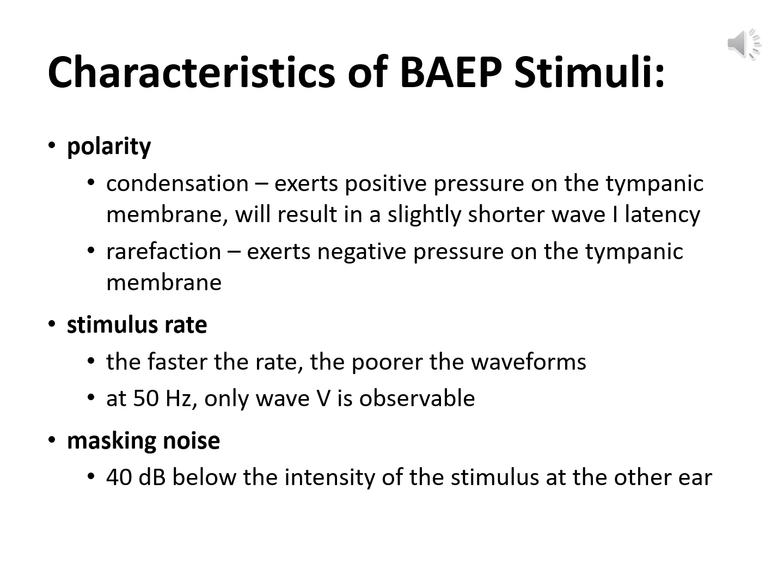In most populations, a stimulation rate of 8 to 10 hertz is recommended. We often use 11 hertz as a starting point. This means we present 11 clicks per second. We can slow the stimulus rate in young children and lower it even further in neonates. Changes to the stimulus rate must be noted on the tracing for the person who is interpreting it. When doing a hearing threshold test where we're only looking at the wave 5, a very fast stimulus rate of 50 Hz is used.